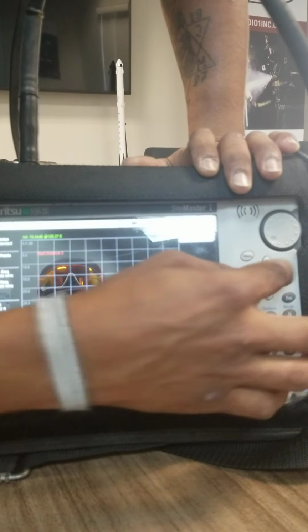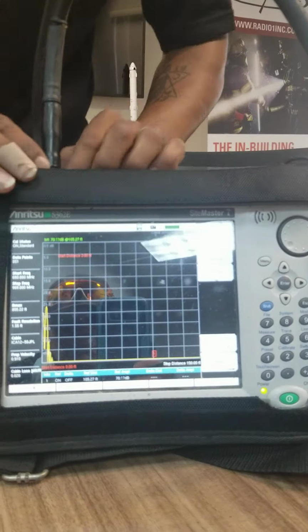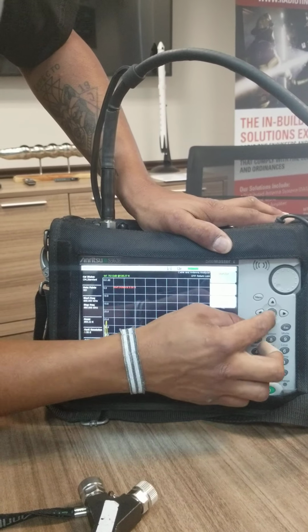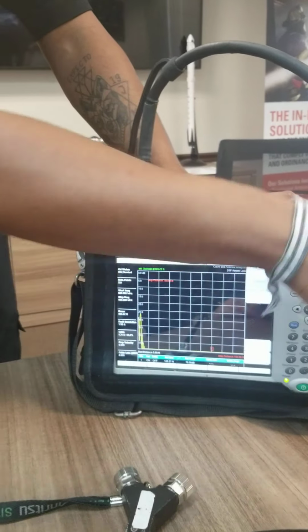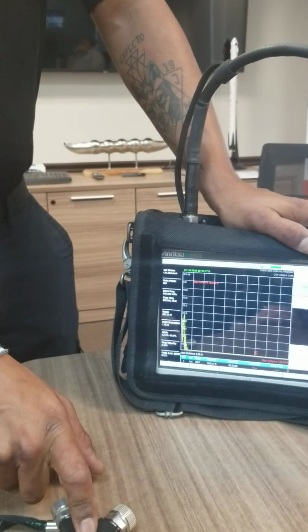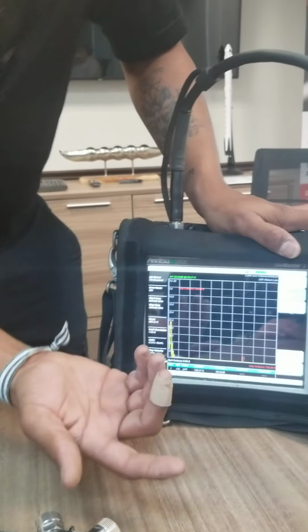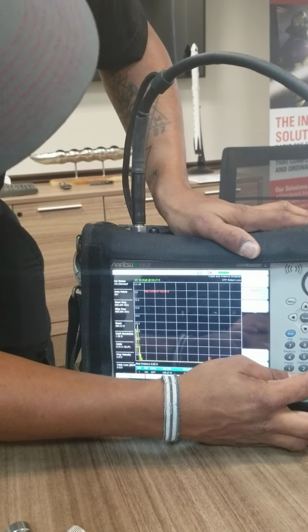Okay. So now, to see the length of the cable, you go here: Frequency and distance. The start is always 0. Because this is your first connection. Always 0, because you start from 0, and then you want to see how far the cable is, where the end is. So start frequency is 0, and then you go to the stop frequency, which is where the cable stops, with the load at the end. So right here we've got a 2-3 foot jumper. 3 feet. So check the weird thing. It's going to look weird since it's a short cable.